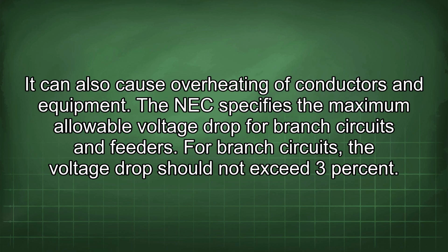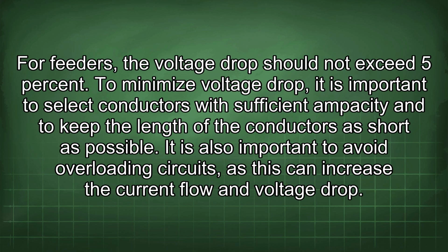For branch circuits, the voltage drop should not exceed 3%. For feeders, the voltage drop should not exceed 5%. To minimize voltage drop, it is important to select conductors with sufficient ampacity and to keep the length of the conductors as short as possible. It is also important to avoid overloading circuits, as this can increase the current flow and voltage drop.